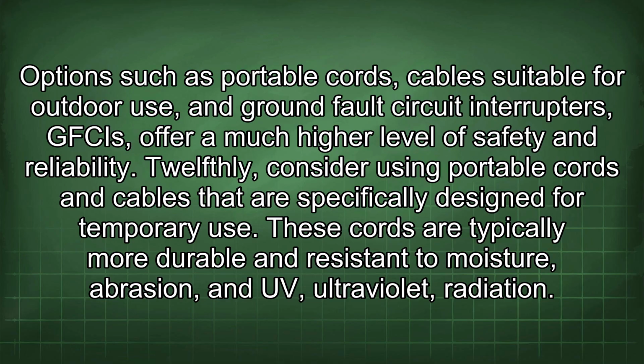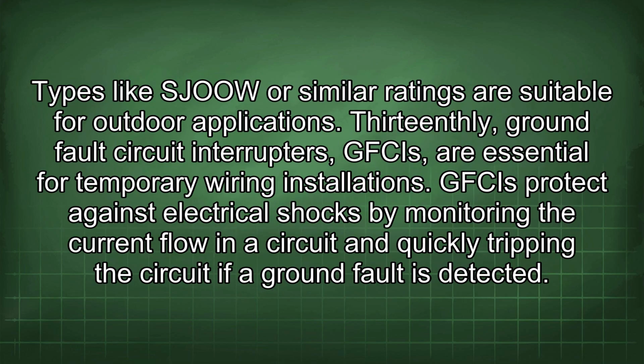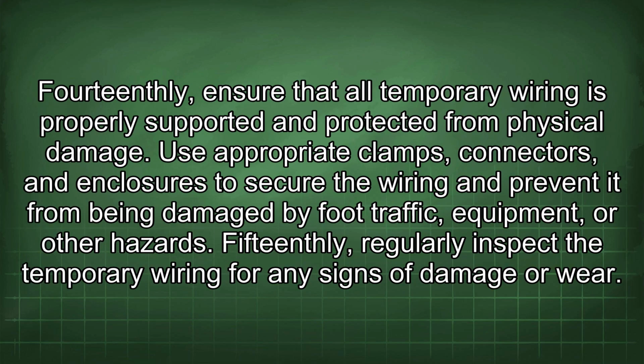12thly, consider using portable cords and cables that are specifically designed for temporary use. These cords are typically more durable and resistant to moisture, abrasion, and UV (ultraviolet) radiation. Types like SJOOW or similar ratings are suitable for outdoor applications. 13thly, ground fault circuit interrupters (GFCIs) are essential for temporary wiring installations. GFCIs protect against electrical shocks by monitoring the current flow in a circuit and quickly tripping the circuit if a ground fault is detected.